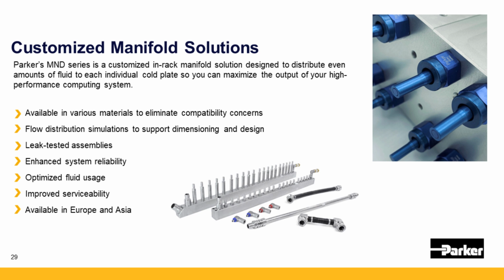The Parker MND series represents a customized in-rack manifold solution designed to distribute the right amount of fluid to each individual cold plate, so the heat is uniformly removed from the processors. The dimensioning and design is made in cooperation and following the customer's installation needs. Flow simulations can support the dimensioning and the internal sections in order to assure the lowest pressure drops and the best flow distribution at all levels. The materials are chosen to assure compatibility with the other circuit elements to avoid corrosion. We also take into consideration easy access and dismounting for maintenance if necessary, in line with the customer's installation.